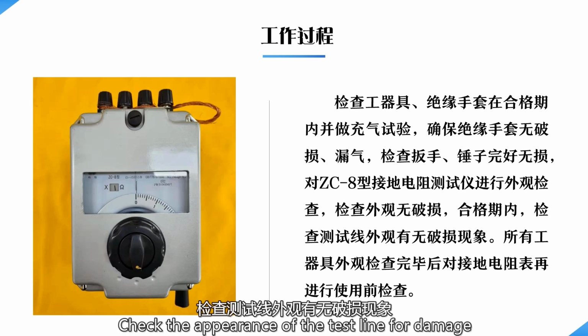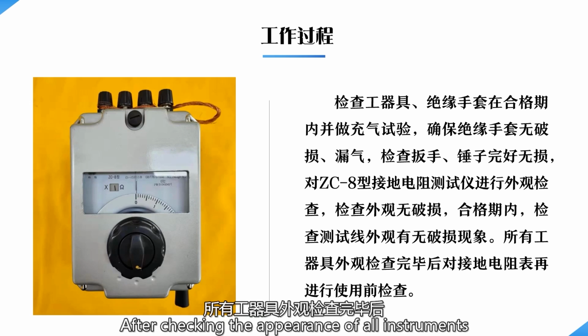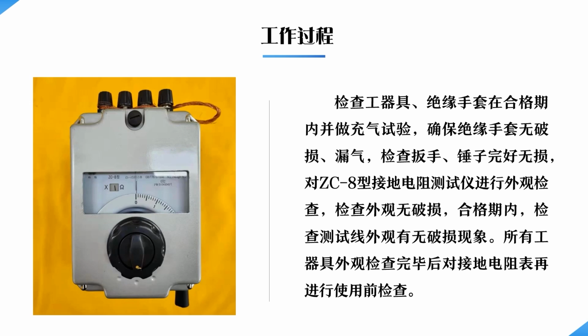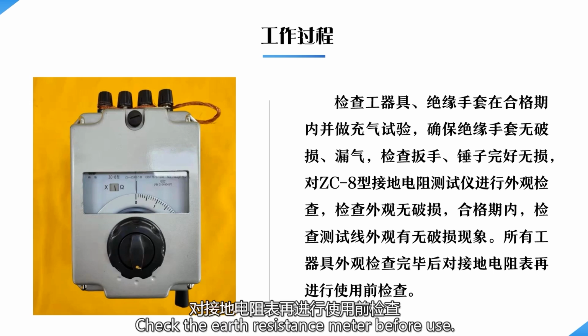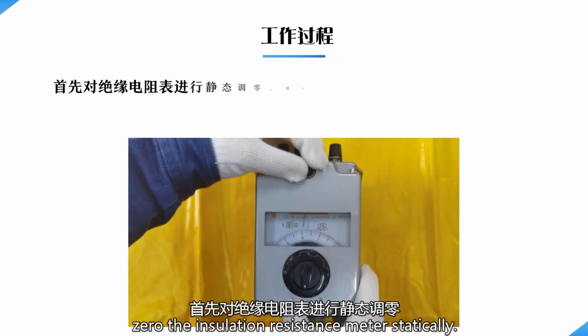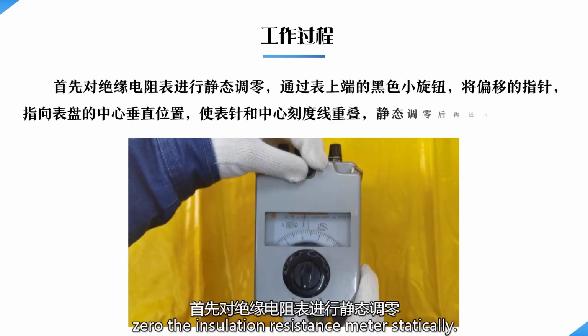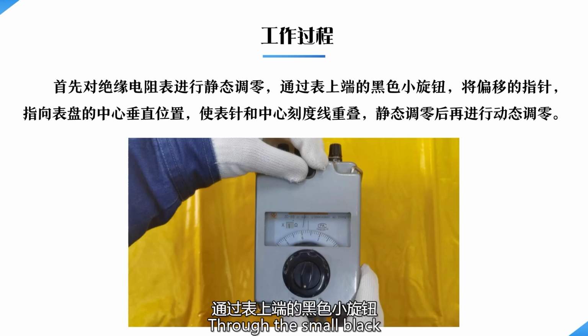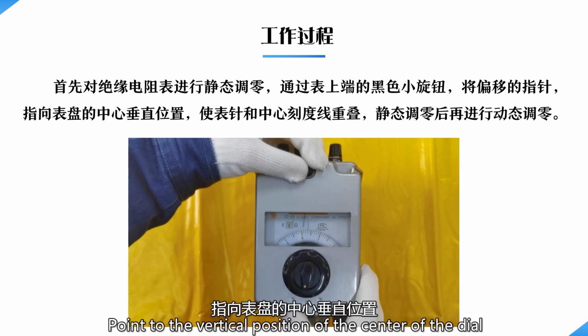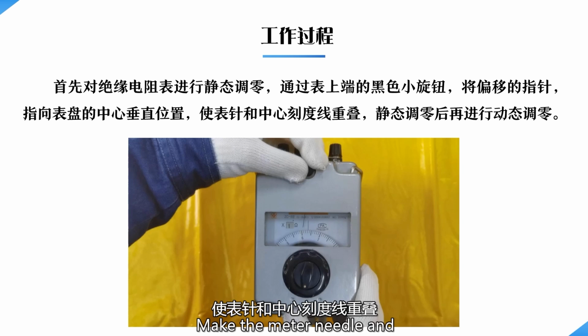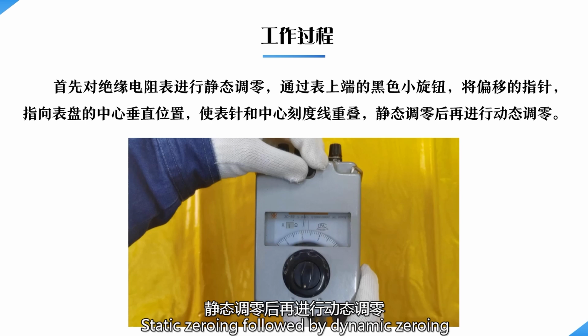Qualification period. Check the appearance of the test line for damage. After checking the appearance of all instruments, check the earth resistance meter before use. First of all, zero the meter statically through the small black knob on the top of the meter. The pointer should point to the vertical position at the center of the dial. Make the meter needle and the center scale line overlap. Static zeroing is followed by dynamic zeroing.